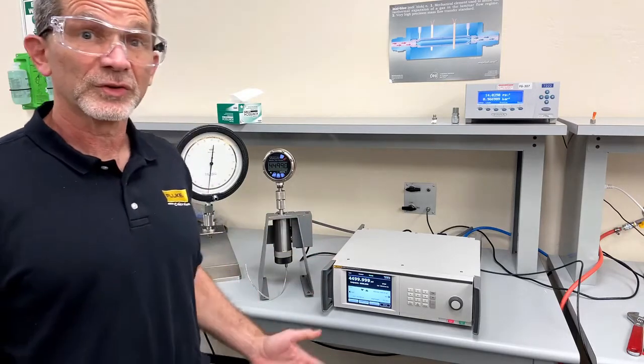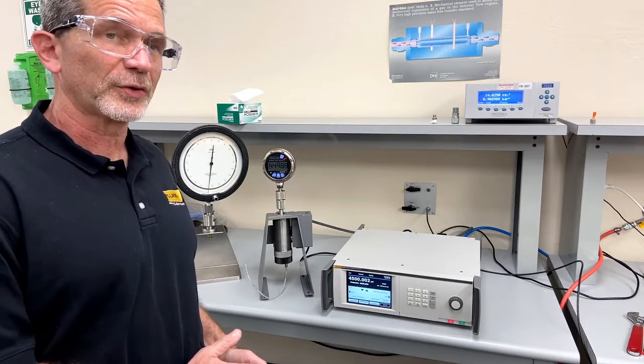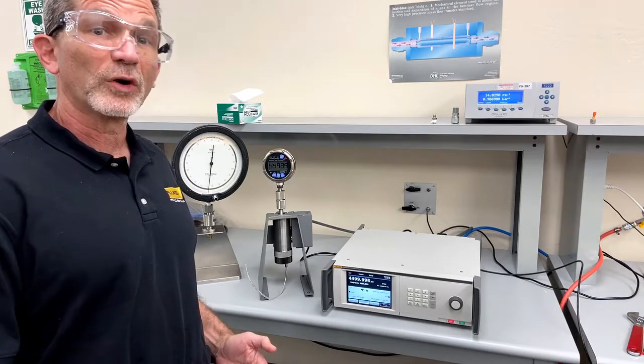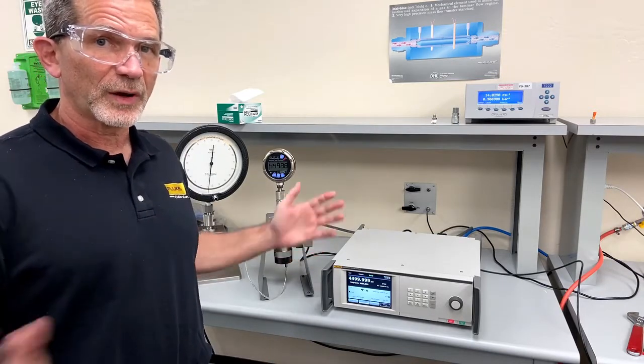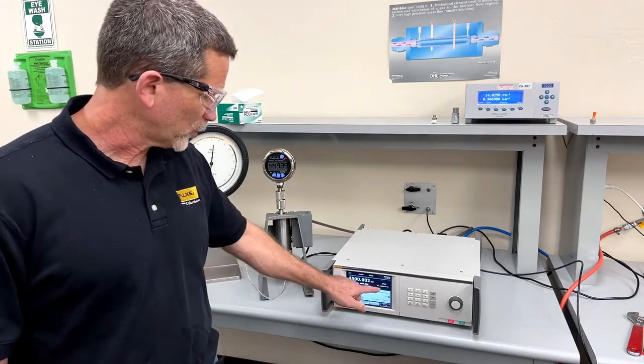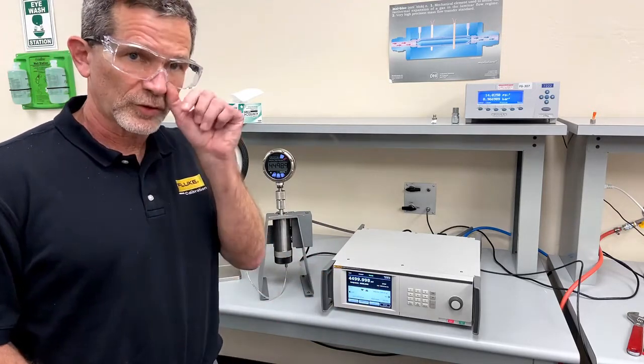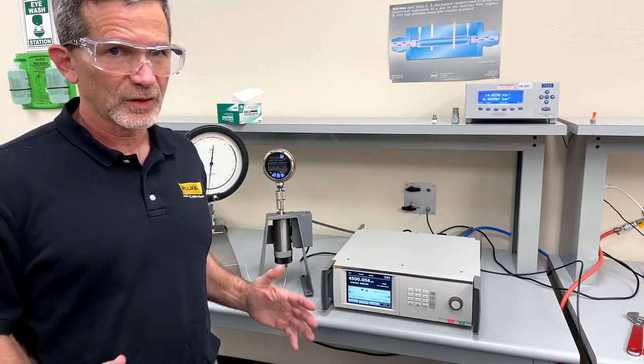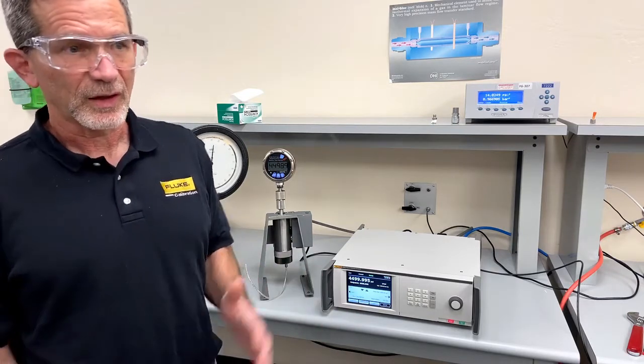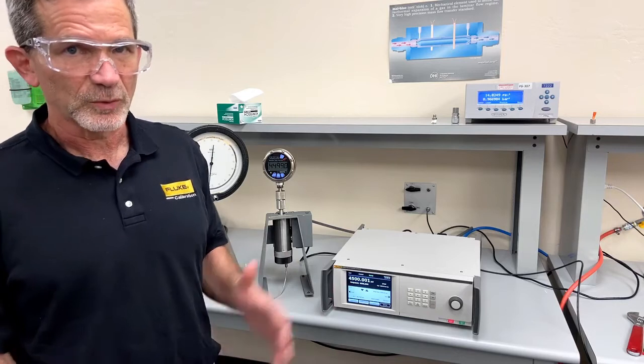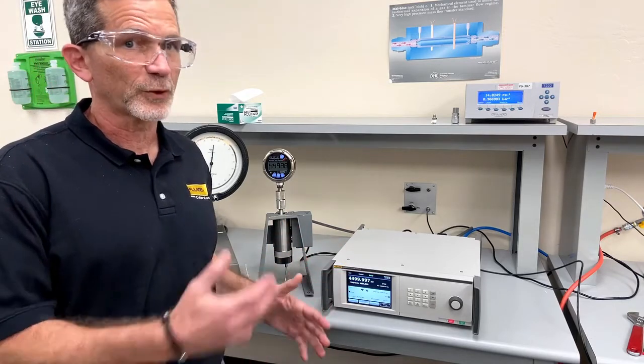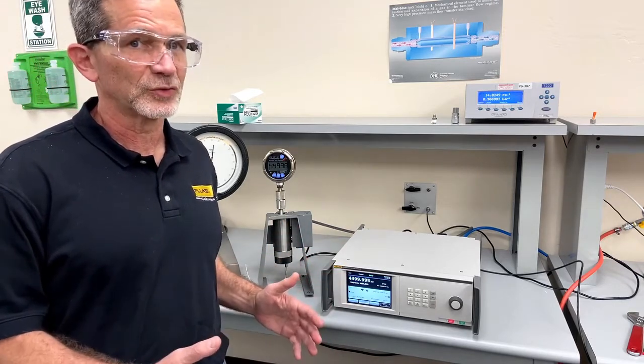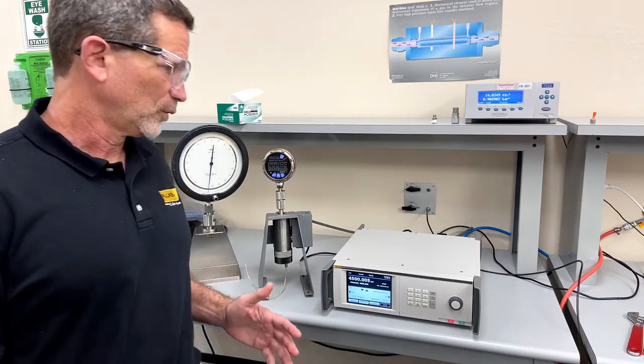Next we're going to go down all the way to 30 PSI to show you how well it controls over a very wide range. By the way, we are in what's called auto mode. So the controller is picking the module that has the best uncertainty for the point we're measuring every time. You do have the option to use fixed mode if you prefer that the same reference module is used every time.